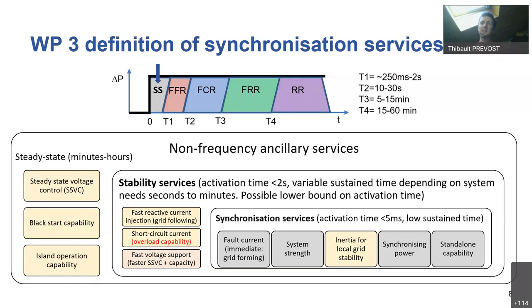So this fault current. Fault current is self-explaining. We have the system strength: when you have a change in the amplitude of the voltage, you need to provide reactive current. Then synchronizing power, when you have a step in the angle, and standalone capability also, which is very different from black start, because we are not talking about being able to provide enough energy to the island. It's just to be able to continue operation for a few seconds or more, and having, for example, a decreasing frequency to provide the signal to the others that this island has been split from the rest of the system.